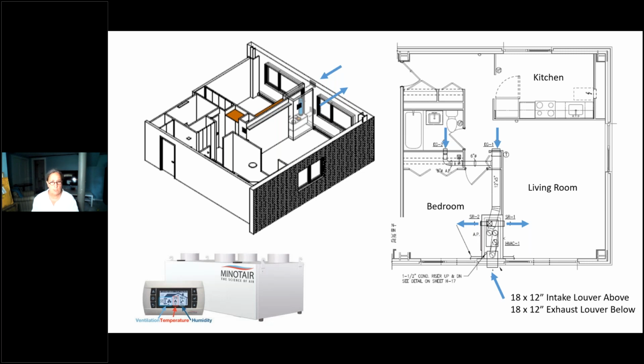Due to some structural constraints in the building - big I-beams we couldn't run ductwork through in the hallway - we ended up using the MinotAir. We installed it in a management office that was a former unit, and only heard good things from the staff about the fresh air. Basically it's heating, cooling, and ventilation in a box. We're building a closet on the exterior with intake and exhaust, acting as an ERV as well as a cooling system. There is a fossil fuel boiler and domestic hot water system, but that heating will be supplemental. Effectively, we have an all-electric heating, cooling, and ventilation system.